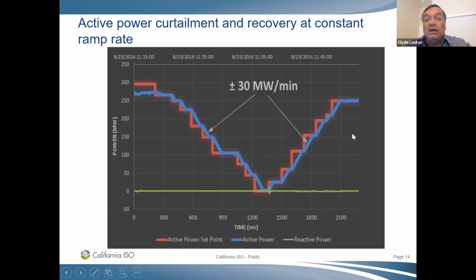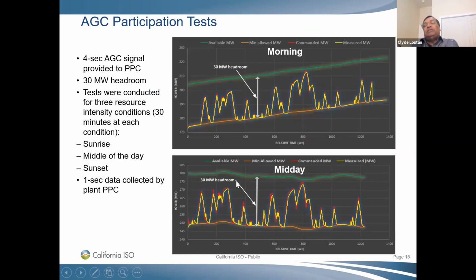It was encouraging to see a solar plant being so responsive to set point signals from the ISO to either ramp down or ramp up. And you can see the reactive power, when we did that movement on the active power, which is your megawatts, the reactive power stayed pretty flat, right? Now, this plot here is really showing the 4-second control. We did this test in 3 different timeframes. We did it during the morning, around midday, and then we looked at how well this plant can respond in the evenings, during sunset. So the results were more or less similar for all three tests.